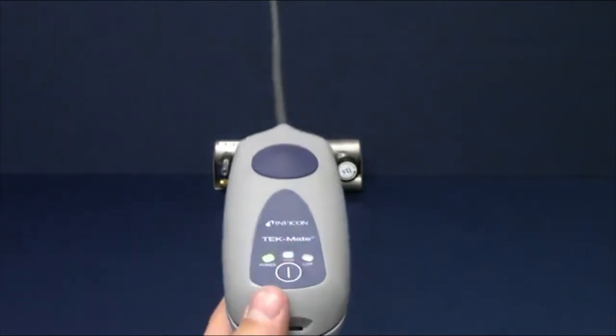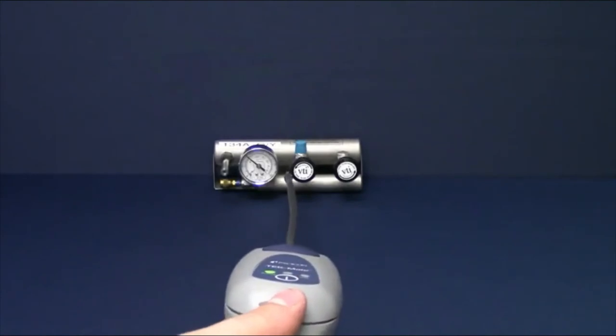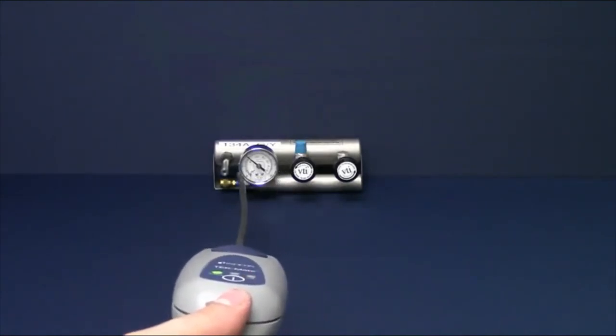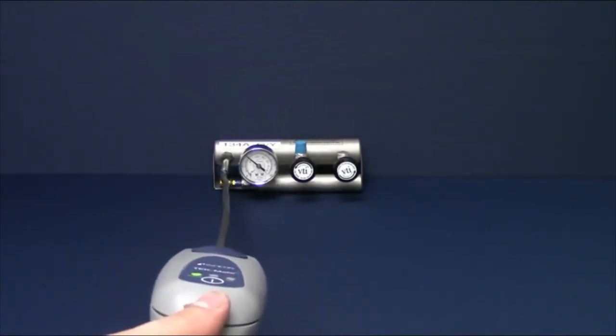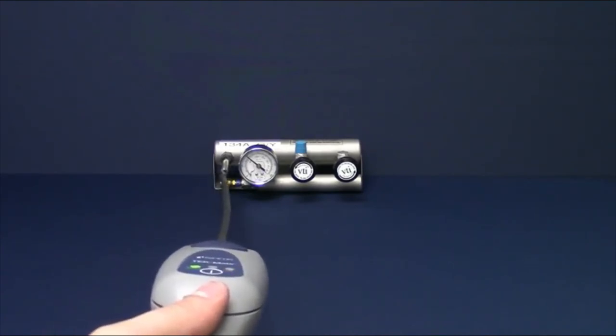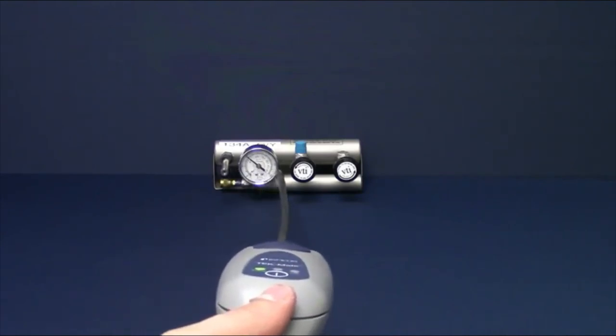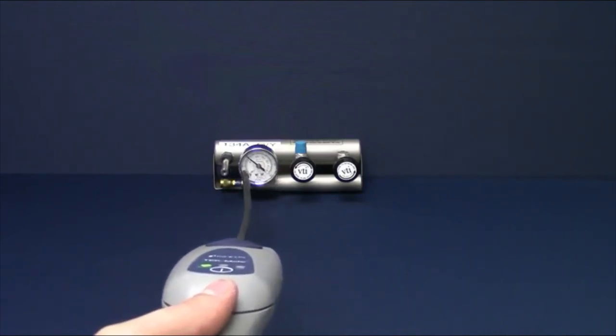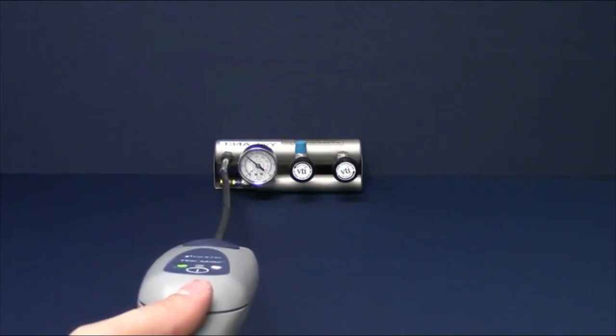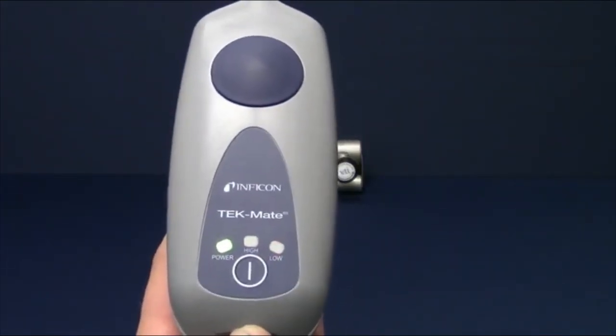Until a continuous beep is heard, move the probe away from the suspected leak for a few moments and repeat to verify. Next, switch to low sensitivity by pressing the power button. Continue moving TEK-Mate through the leak source to narrow it down to a specific point. Note that keeping the probe in the same concentration of refrigerant for an extended time will zero TEK-Mate to that concentration; moving the probe away resets the zero point.